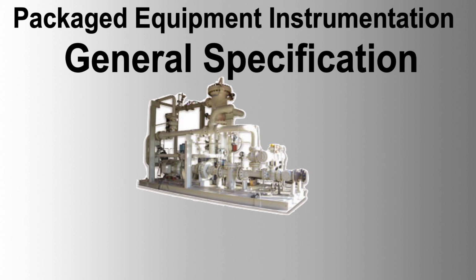Labeling and ferruling. All control panels, relay boxes, and terminal boxes should have nameplates with engraved labels. Instrumentation should have permanently affixed stainless steel labels with tag numbers, and field instruments should have traffolite labels with tag numbers and service. Cables will contain only tag numbers. These general technical requirements ensure that the instrumentation for packaged equipment meets operational, safety, and performance standards for reliable and efficient operation in specified environments.